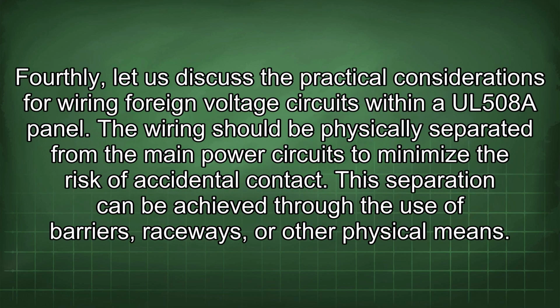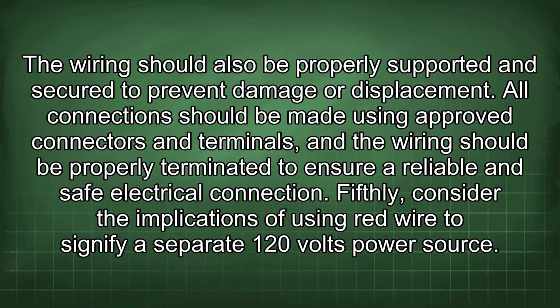Fourthly, let us discuss the practical considerations for wiring foreign voltage circuits within a UL508A panel. The wiring should be physically separated from the main power circuits to minimize the risk of accidental contact. This separation can be achieved through the use of barriers, raceways, or other physical means. The wiring should also be properly supported and secured to prevent damage or displacement. All connections should be made using approved connectors and terminals, and the wiring should be properly terminated to ensure a reliable and safe electrical connection.